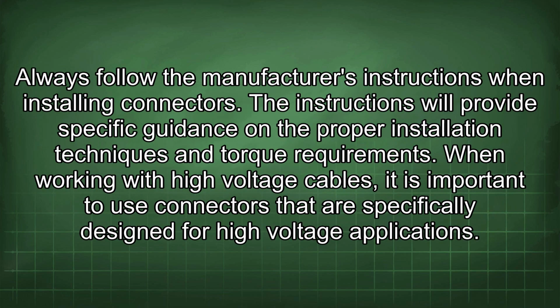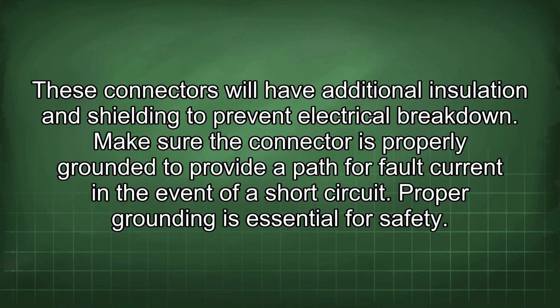Always follow the manufacturer's instructions when installing connectors. The instructions will provide specific guidance on the proper installation techniques and torque requirements. When working with high voltage cables, it is important to use connectors that are specifically designed for high voltage applications. These connectors will have additional insulation and shielding to prevent electrical breakdown. Make sure the connector is properly grounded to provide a path for fault current in the event of a short circuit. Proper grounding is essential for safety.